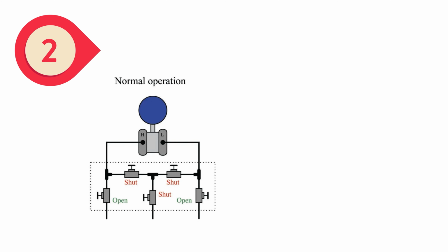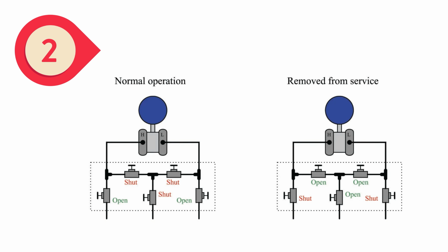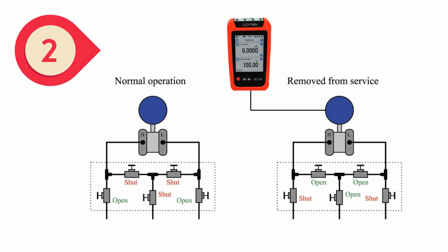Isolate the transmitter from the process. For pressure transmitters, apply zero pressure, or atmospheric pressure for gauge pressure transmitters. Access the transmitter's adjustment mode, usually via buttons on the device or through calibration software. Follow the instructions to set the transmitter's output to zero.